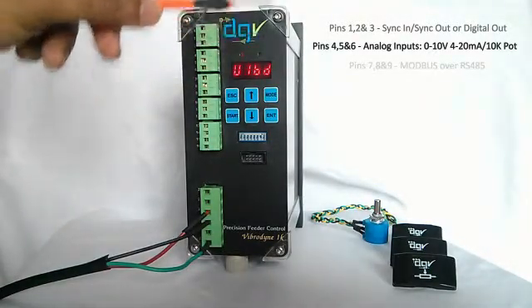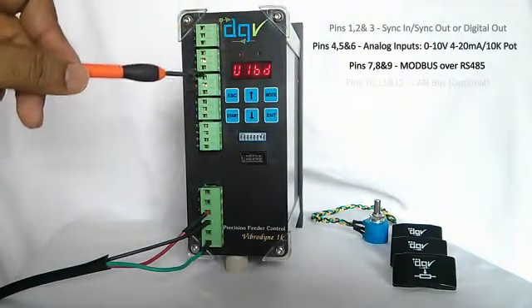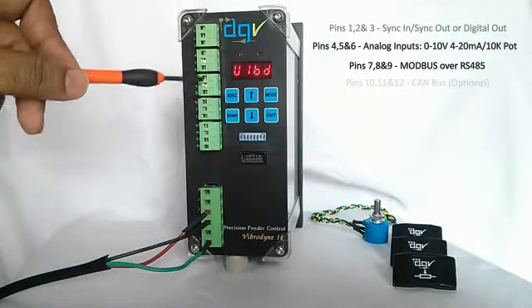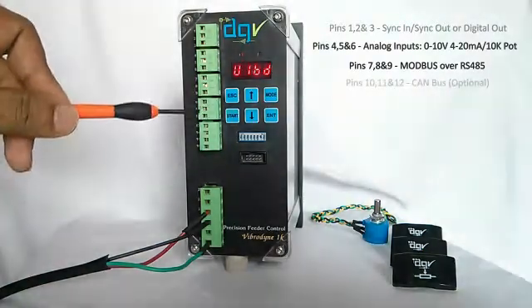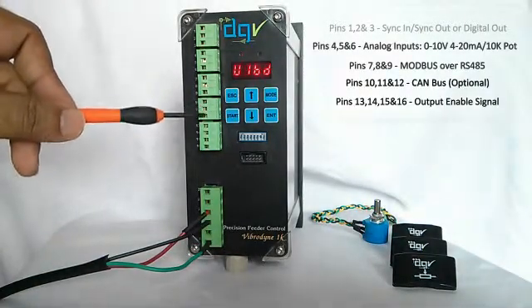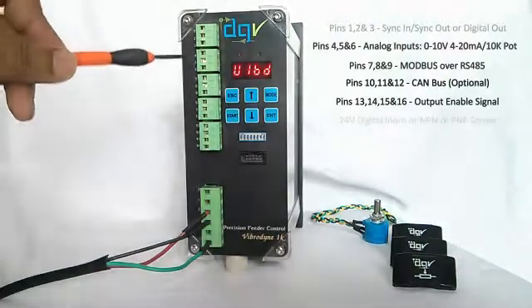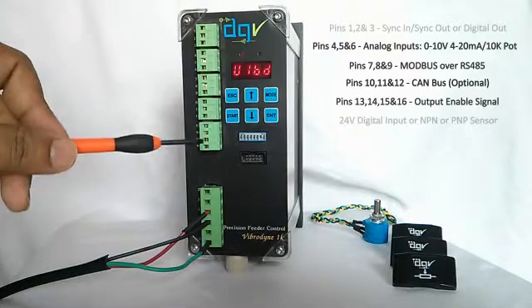The next three are for Modbus. This controller comes with Modbus over RS485 — you can directly interface it to your PLC or higher-end systems. This is where you make the RS485 connections. The next three are for CAN bus connection. CAN bus is not actually being used at the moment. Sync and CAN bus are two things we will talk about later.